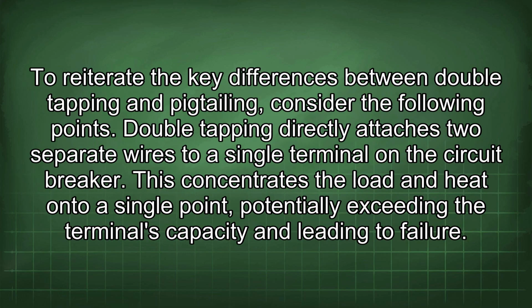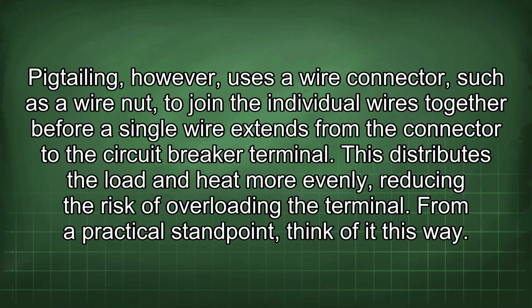To reiterate the key differences between double tapping and pigtailing, consider the following points. Double tapping directly attaches two separate wires to a single terminal on the circuit breaker. This concentrates the load and heat onto a single point, potentially exceeding the terminal's capacity and leading to failure. Pigtailing, however, uses a wire connector, such as a wire nut, to join the individual wires together before a single wire extends from the connector to the circuit breaker terminal. This distributes the load and heat more evenly, reducing the risk of overloading the terminal.